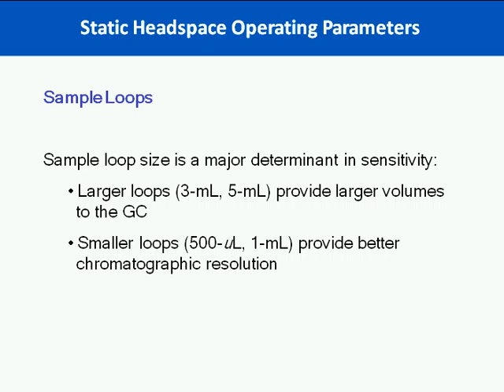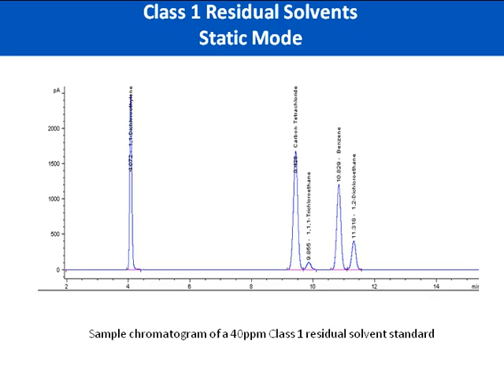In terms of the sample loops used in headspace analyzers, you have to balance the factors described. When the analyzer steps to fill the sample loop after the vial has been pressurized, probably the best way to determine the optimal loop fill time is to attach a flow meter to the vent and monitor the flow. Larger loops, like your 3 and 5 mil loops, are going to provide larger volumes going to your GC, while your smaller loops — 100, 250, 500 microliter, and even 1 mil — are going to provide better chromatographic resolution.